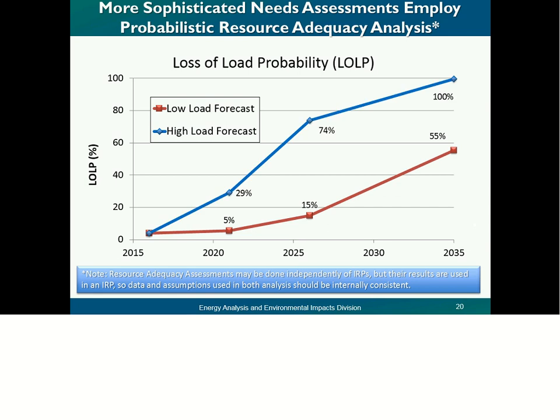And as a consequence, you're looking at the probability of, in this case, the loss of load probability. On a Northwest basis, it's resource adequacy on a 5% loss of load probability. It means there's a 95% probability we'll keep the lights on, not 100%, because that would lead to overbuilding given the policies that we have. And we can take extreme measures like interrupting large industrial contracts to still meet loads. But this means before we have to take extreme measures, before the governor gets on the phone and calls the media, we have a 95% probability of meeting loads.